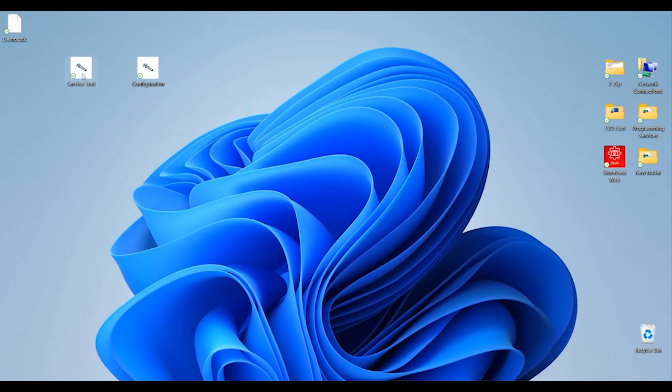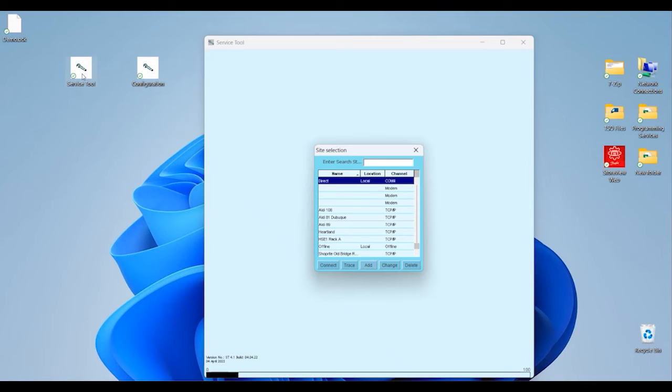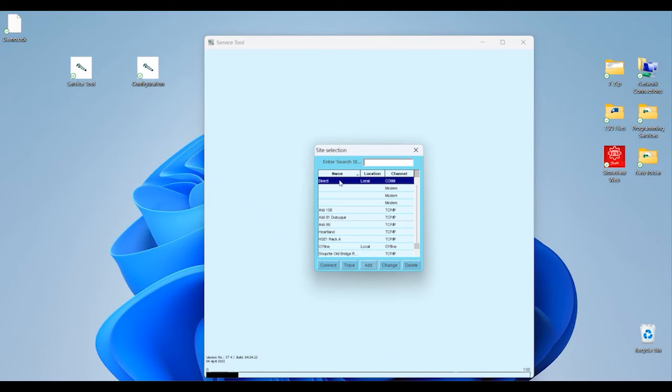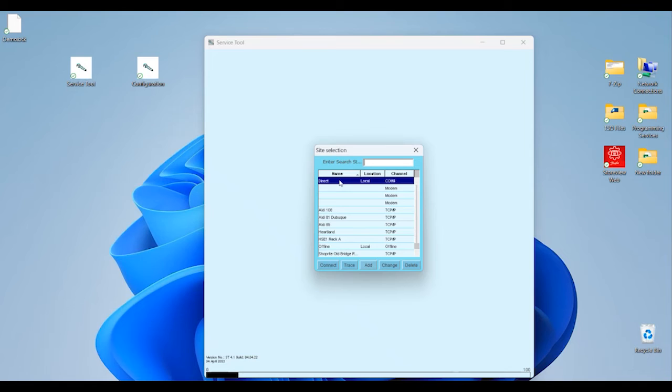Here we get a pop-up and we have different options for the types of connections. You can view files offline, you can make that local direct connection which is the option highlighted here over a USB cable, and there are some remote capability options for pack controllers through service tool. Certain things have to be in place - the pack controller has to be tied into a system manager and the network switch router that we're using has to have specific ports open to allow us to tunnel in through the system manager into the pack controller.